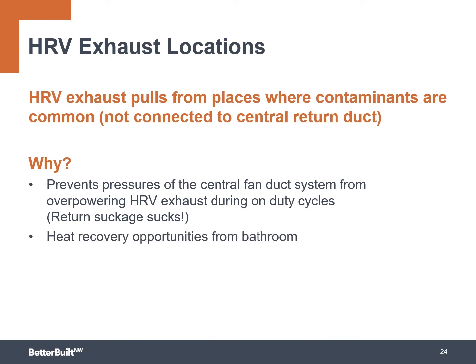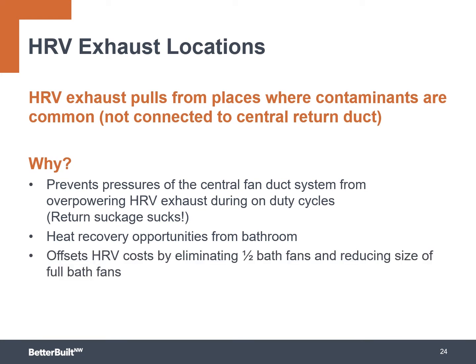HRV. Heat recovery opportunities from our bathrooms are good. Steamy, moist, wet, warm air has a little bit more heat to transfer out of it typically, so that can improve our incoming airstream temperature. This again offers that ability to offset the HRV costs by maybe even eliminating fans in half bathrooms and utility closets and reducing the size of fans necessary for those full bathrooms.